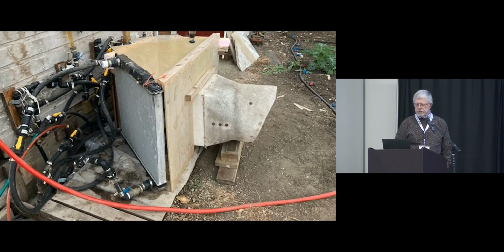Hard to see in this picture, but the line at the bottom of the radiator is where the water comes out of the ground and goes into the heat exchangers. There's a temperature port there. The heat exchangers are in series, and the last one has a line that goes back into the ground, with another temperature port there. So with that, and with the flow meter you saw in an earlier picture, I can calculate what the heat flux is.